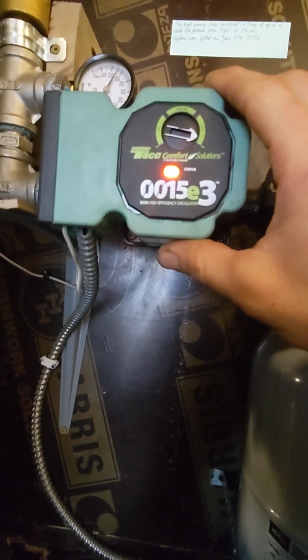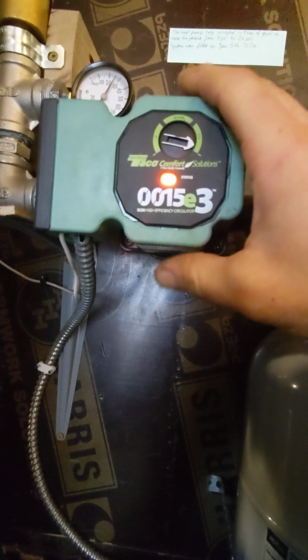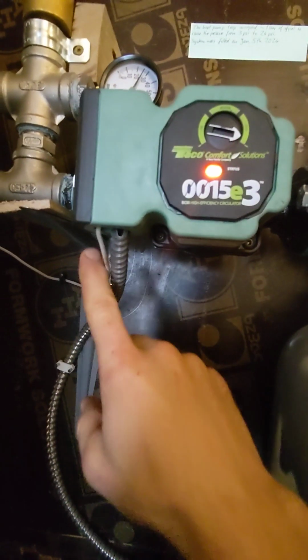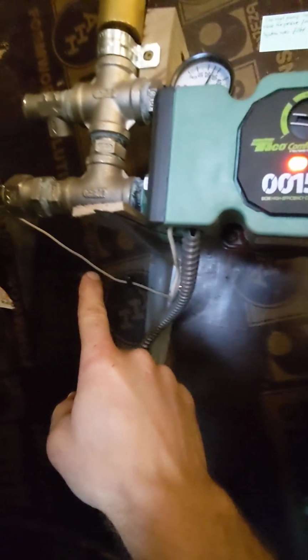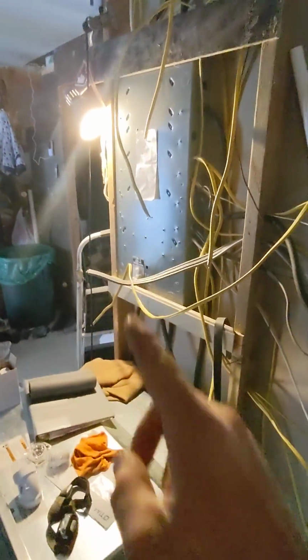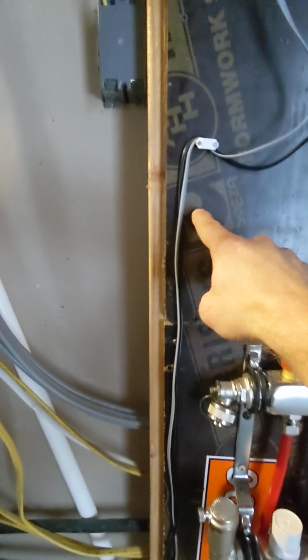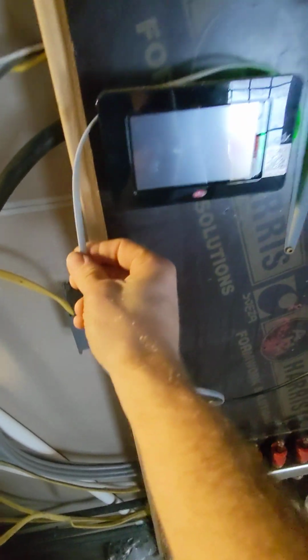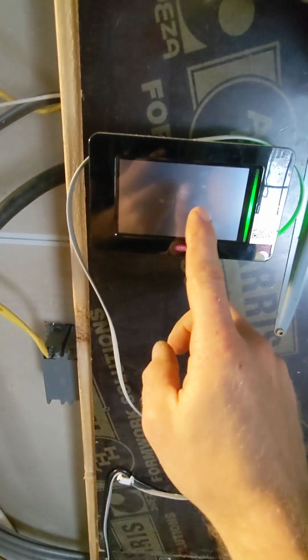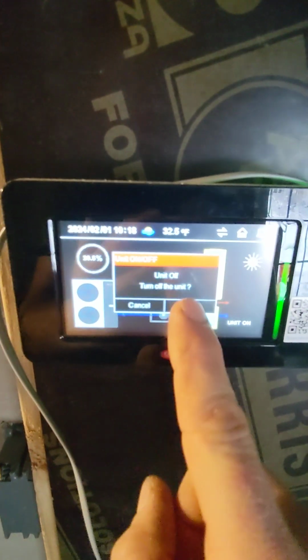So the heat pump outside is entirely controlling that circulator. And then I just have a white neutral wire that runs back to my breaker panel to complete the circuit so that the pump runs in the first place. Now, again, the communication wires, I just have them tacked temporarily into place right here. This is the gray controller wire cable that goes into the controller, that you can turn the unit on and off.